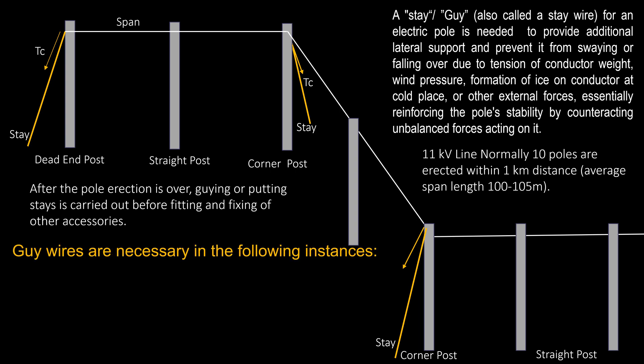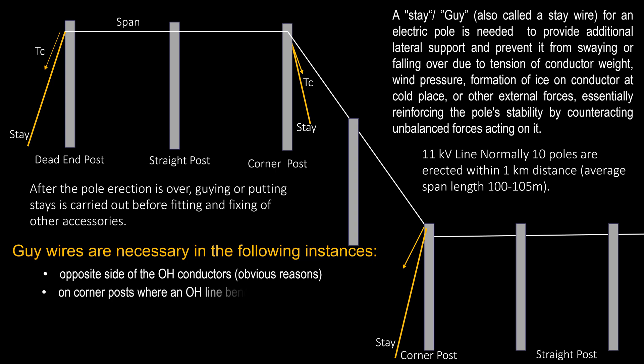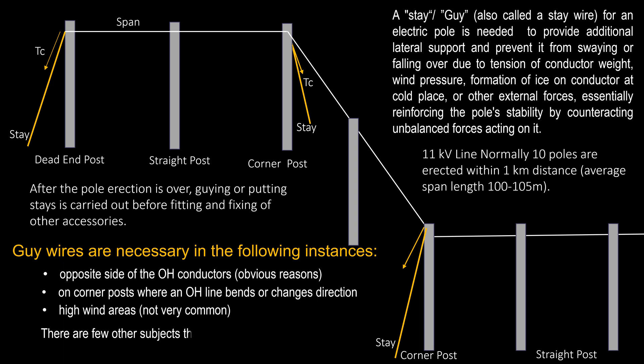Guy wires are necessary in the following instances: on the opposite side of overhead conductors; on corner posts where an overhead line bends or changes direction; in high wind areas. Tension exerted by the weight of conductors on poles from both sides of the span may displace or bend the pole, and this can be counterbalanced by providing a stay at a suitable position.